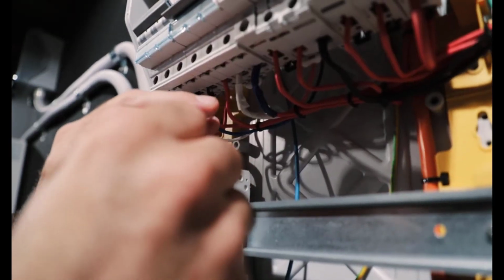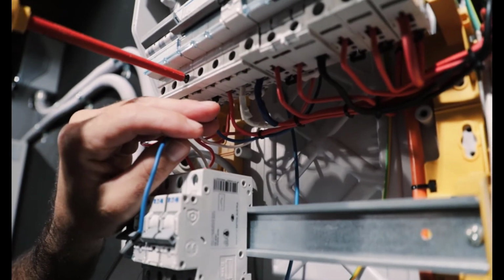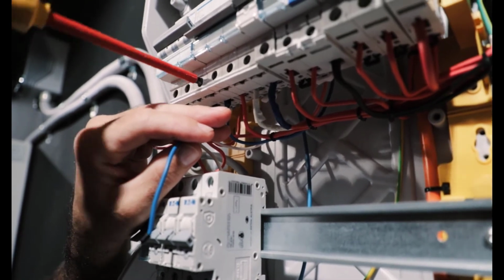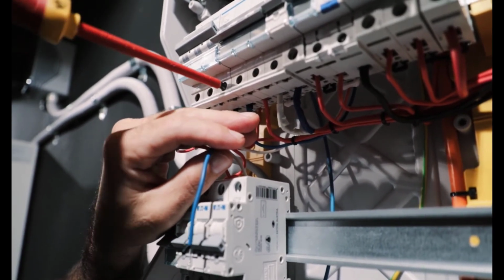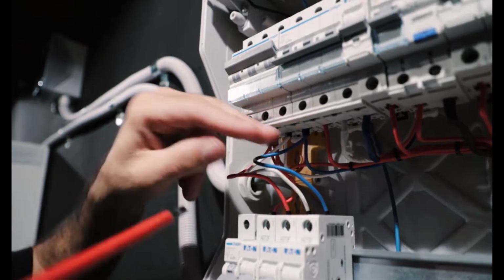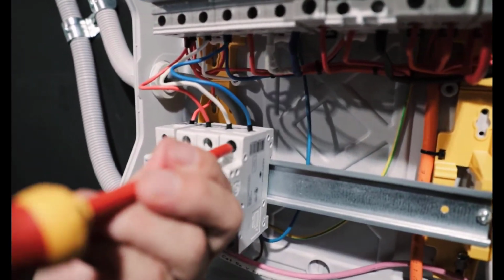Now the meter itself is not a three-phase load. It will happily operate on 1 or 2 or 3 phases, so it doesn't need to be a latched three-phase MCB.